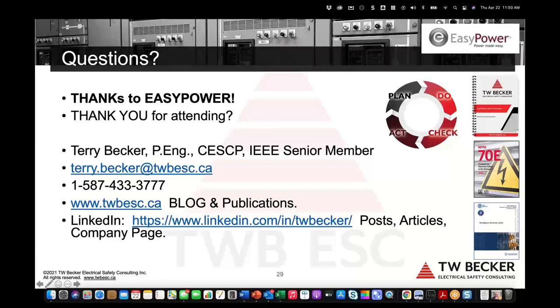Between the VCB and the new VCBB box electrode configuration, you're going to find the results are going to be very similar to the 2002 formulas. The other thing too is, based on what I own, do I have low and high voltage switchgear and high voltage MCCs? Do I have any electrical equipment that would have an HCB box electrode configuration? Because then that's where I'd want to prioritize doing the calculations.